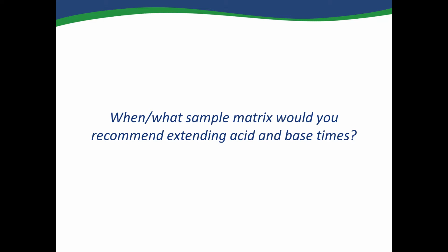What sample matrix would you recommend extending acid and base times? I'm not aware of any. The method calls for strict adherence to the times that are programmed in there. So I don't believe that you would want to extend the time for digestion. You wouldn't be running the method correctly if you did that. So just stick with the programs on the A2000 as written.